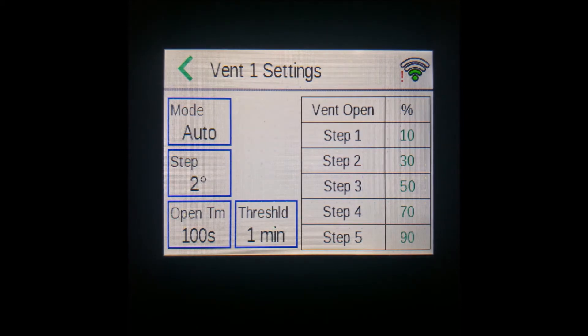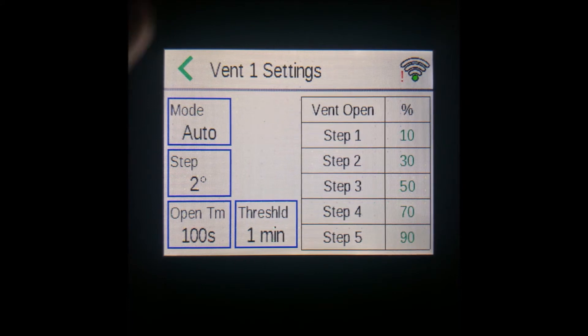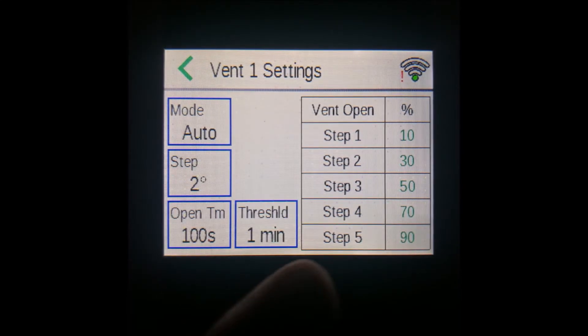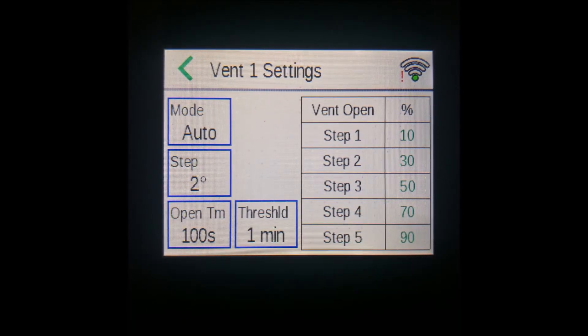If the target temperature is 65 and the current temperature is 71 degrees, for example, that's three steps above, so your controller will have the vent open to step 3, which in this case is 50%. This is what will happen if the mode is set to auto.